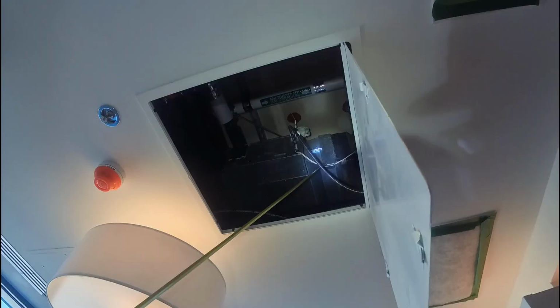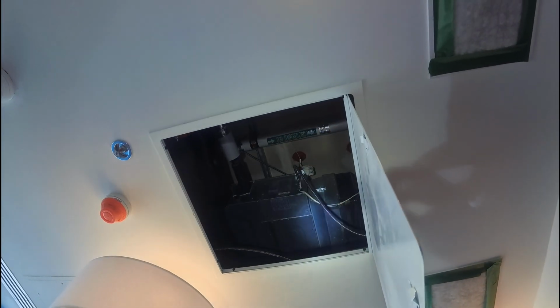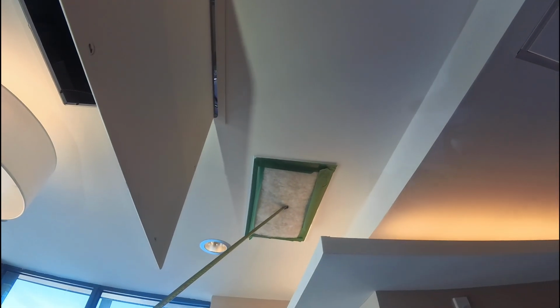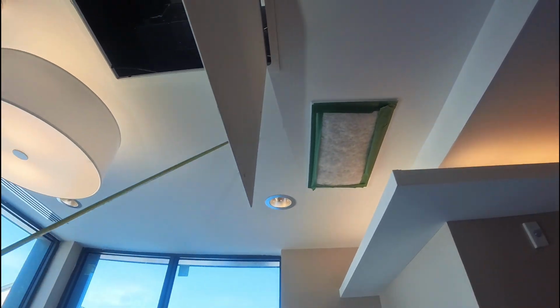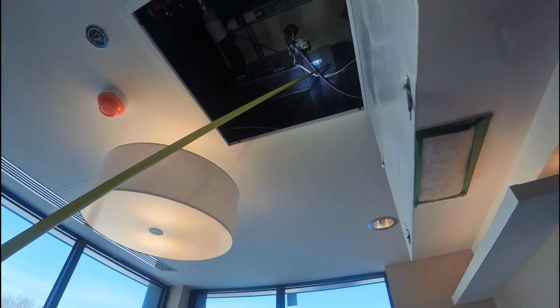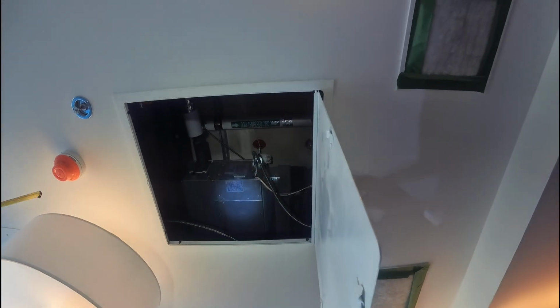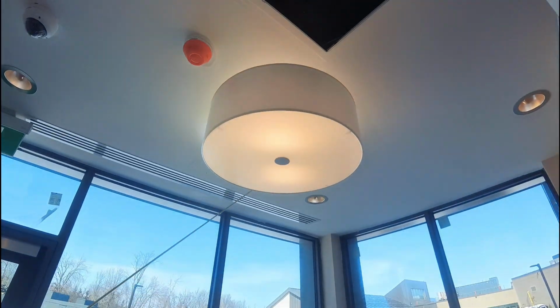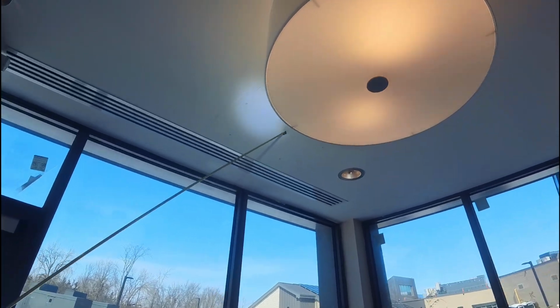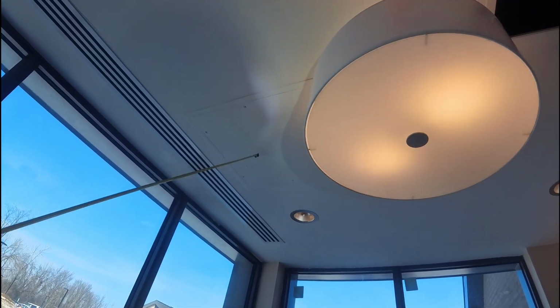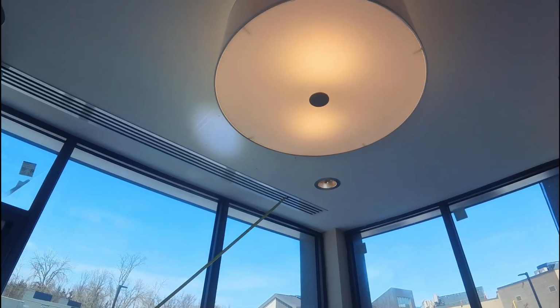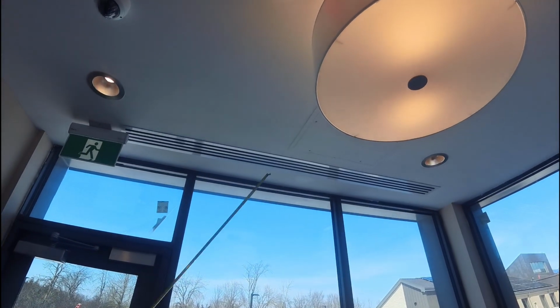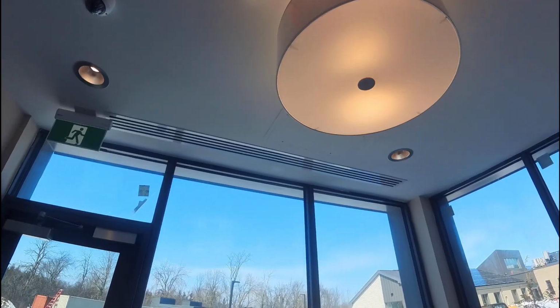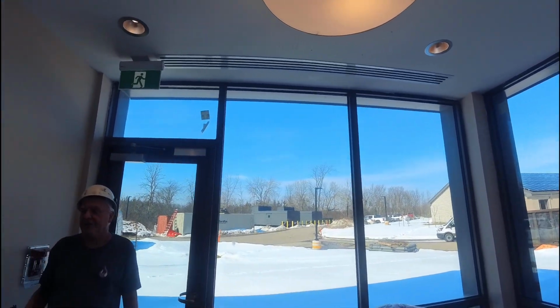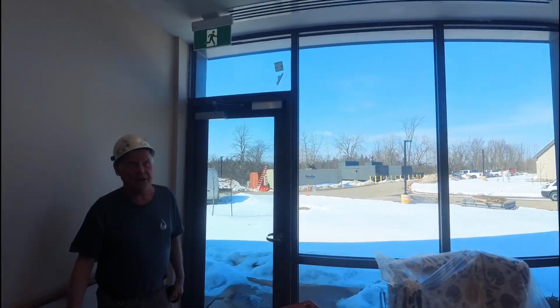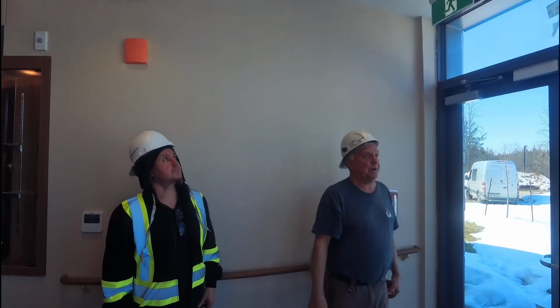Again, this is going to be your return end. Based on looking, you can tell your return end by the exhaust inside, or the return air inside, with your filter rack, and your supply filter rack would be over here, which you'd have access through this door here if required. But that door also has 2 balancing dampers that are associated with the linear grill, which have already been preset, and they've gotten their readings. This has all been balanced, and the airflows are adequate here.